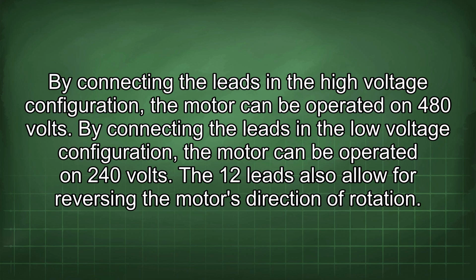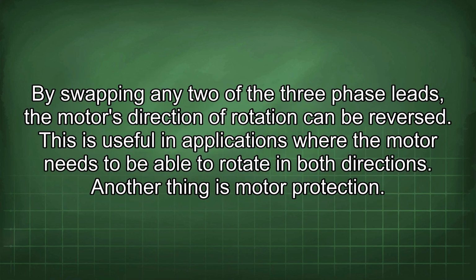The 12 leads also allow for reversing the motor's direction of rotation. By swapping any two of the three-phase leads, the motor's direction of rotation can be reversed. This is useful in applications where the motor needs to be able to rotate in both directions.